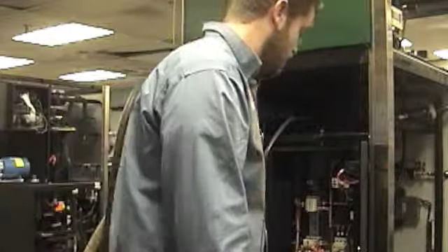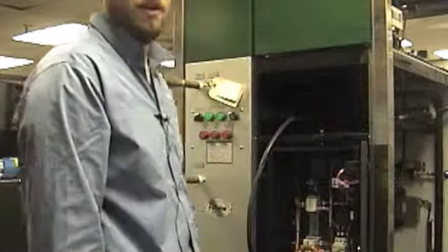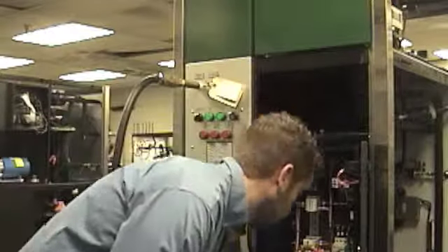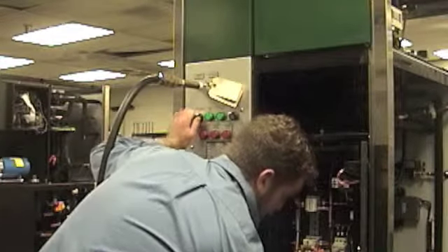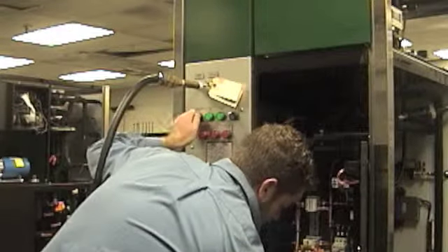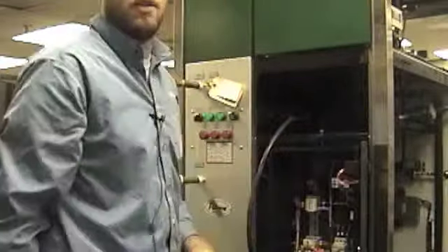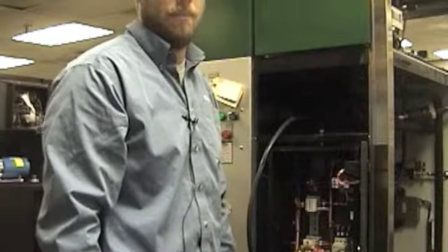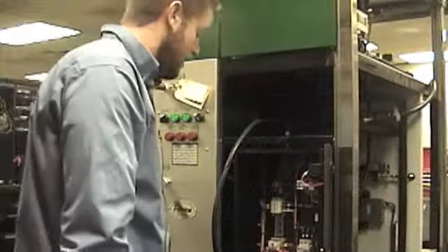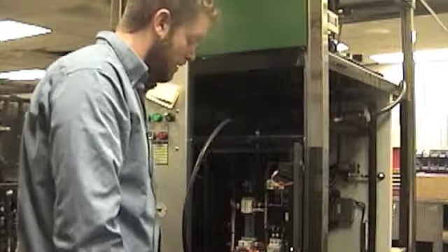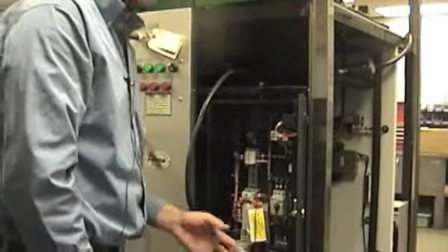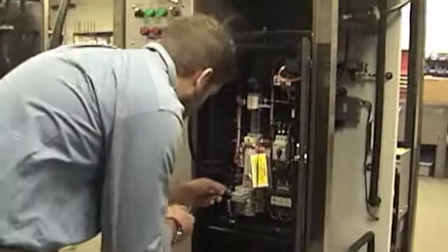So what we can do is, if you have an assistant, they can look at the rotation, or if you're pretty skilled, you can look at it and we'll bump it on. And this one is reversed, so we're going to have to switch the legs on it. Because the pump rotation didn't match the sticker on the pump for the right direction, we're going to have to reverse 2 of the legs on this pump.